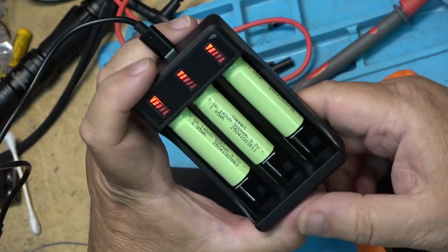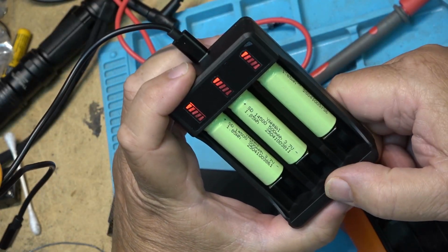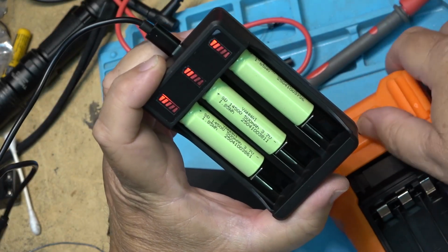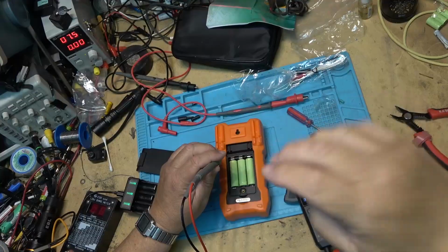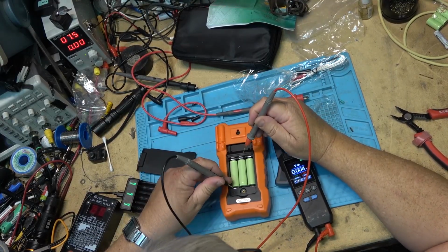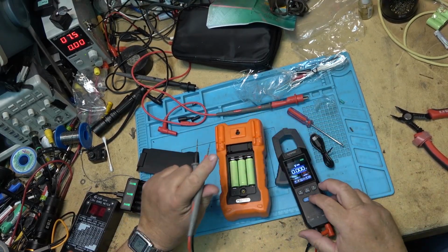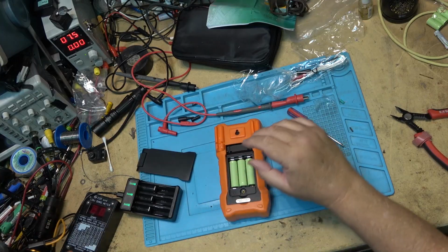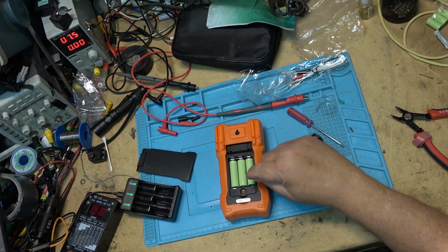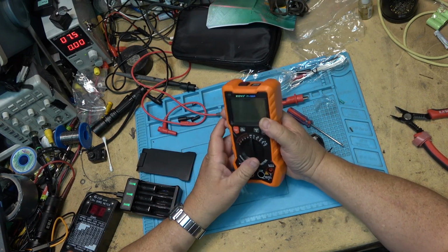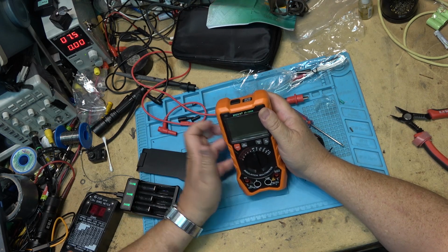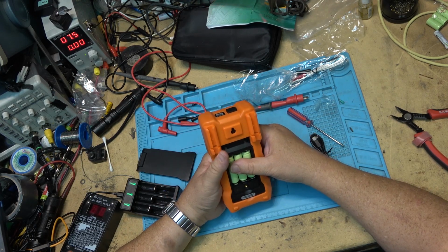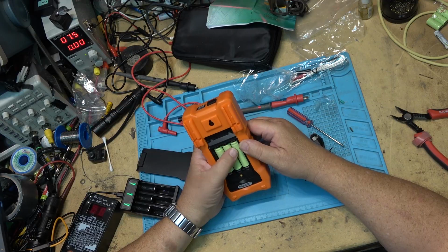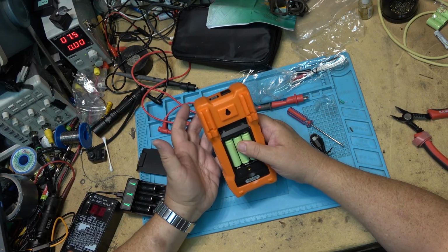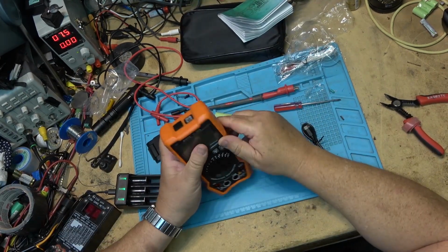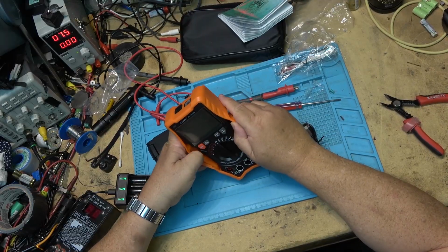Now the advantage to that is, well, they're rechargeable and they're lithium, so they're going to last a long time. The downside, of course, is you can't just put regular AA cells in. This meter does indeed operate on 12 volts. And the reason it's going to do that is, again, because of the high voltage generator that's in here to generate the breakdown. So we're starting at a higher voltage, which is easier to step up than a low voltage. So no, you're not using regular alkaline cells in here. And according to the manual, it does not accept anything other than the lithium cells.